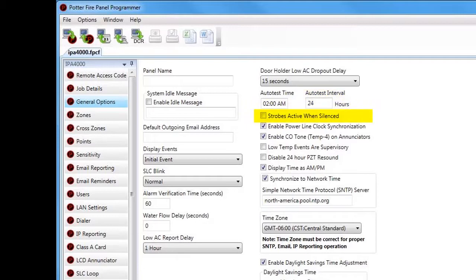Next is Strobes Active When Silenced. If you would like the strobes to remain active when the panel is silenced, you need to check this box. The default is unchecked — when unchecked, pressing the silence button will silence both the strobes and the horns. If you want the strobes to remain on, check this box and when you silence the panel the strobes will remain active.